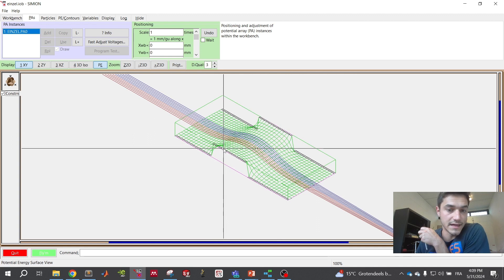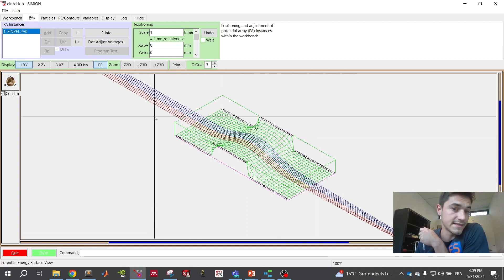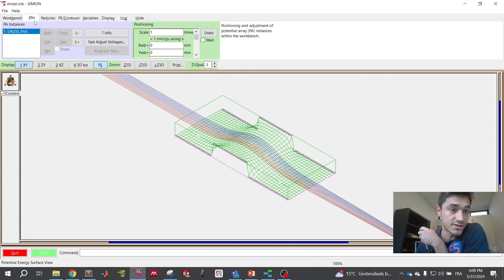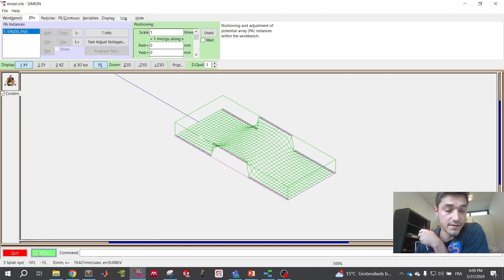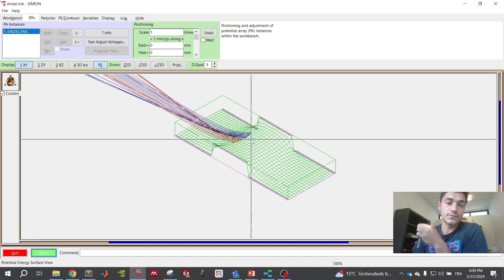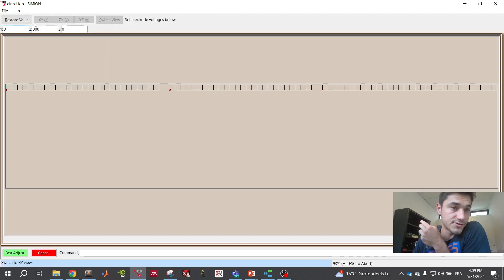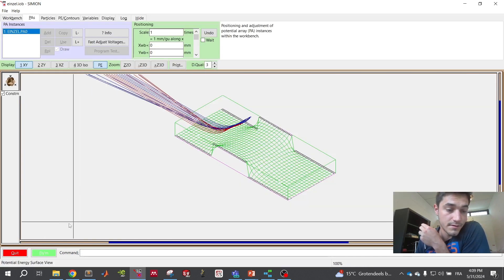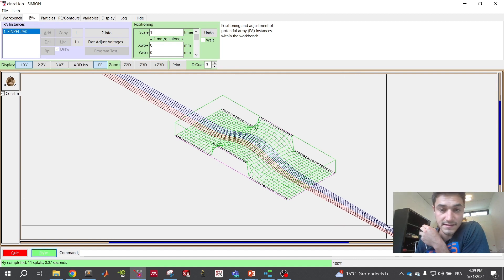The potential of the center electrode must not exceed the kinetic energy of the ions. Currently the center electrode potential is 110. If you change that to 300 — higher than the ions' kinetic energy of 200 — and fly the ions, you can see the ions don't have enough energy to pass the first potential hill. You can then fast-adjust back to 110, and now the ions are able to pass through that hill again.